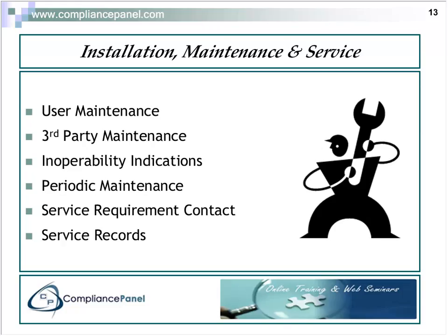How are you going to record your service records as these go out? Maybe in the back of your maintenance manual you have a form that someone fills out if maintenance is required. Now, obviously some devices are so simple that it either works or it doesn't, or it's disposable and thrown away, so there are no service requirements there. But again, all this is part of the device master record, and third-party maintenance becomes tricky because a lot of hospitals now will use third-party people to come in and maintain their equipment, like outsourcing their biomed technicians.